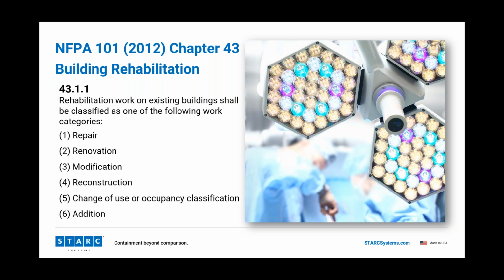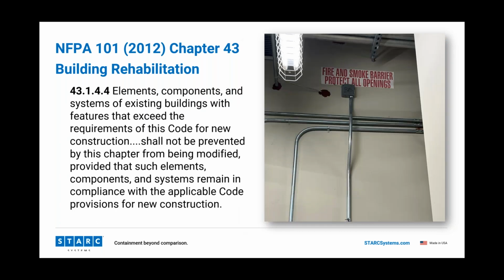I've got a few things we'll talk about here from a definition perspective, just to level set. One thing, and I tie this section back to Chapter 4, which is a fundamental chapter. It's the general requirements chapter. When you have an existing building that exceeds the requirements of new occupancy chapter construction, you can bring that down to what the new chapter requires. Let's just say, as an example, that you have a 2-hour wall that was built in the 70s for whatever reason, and the new occupancy chapter says that only a 1-hour wall is required. Then you can derate that wall from 2 hours to 1 hour.